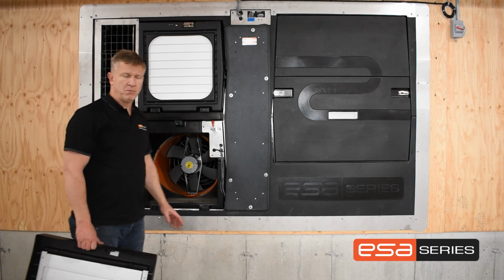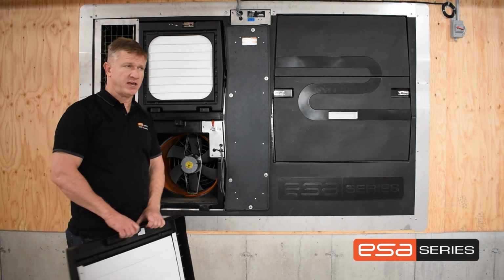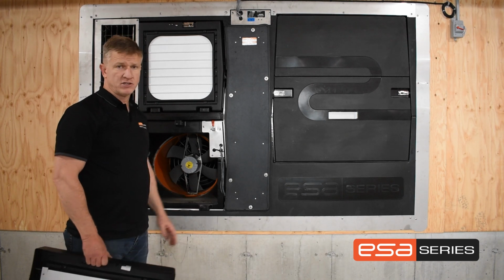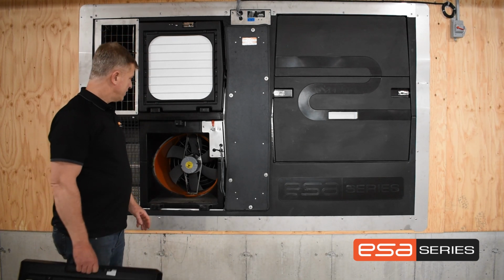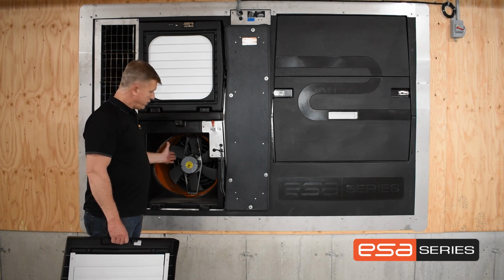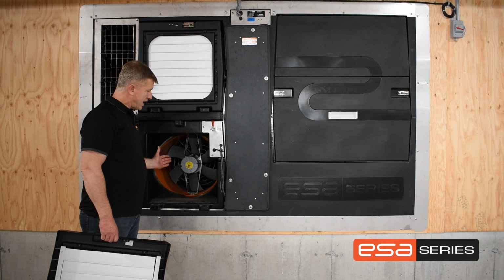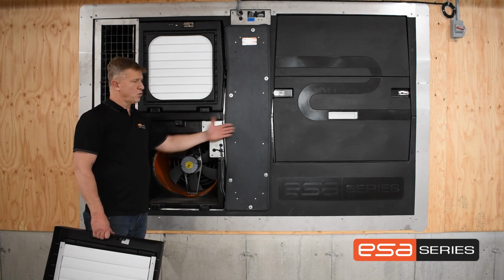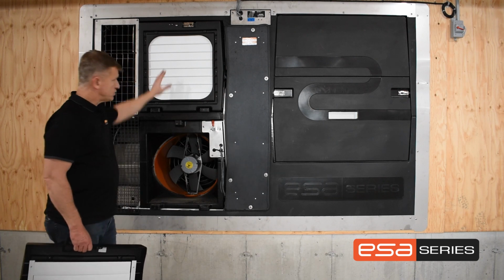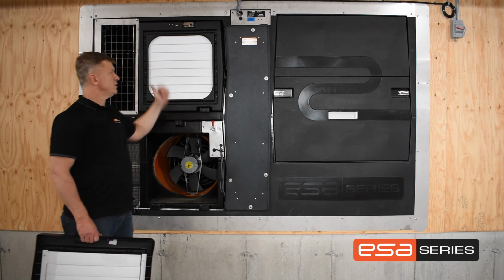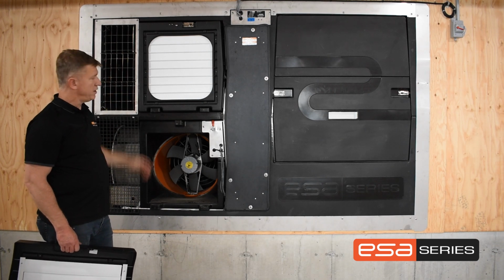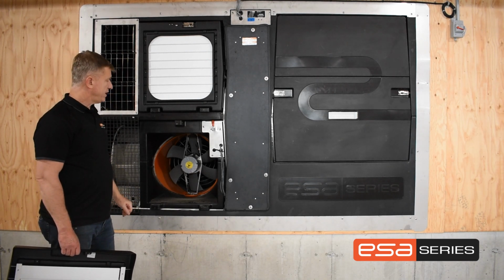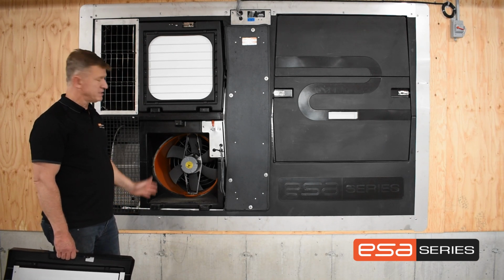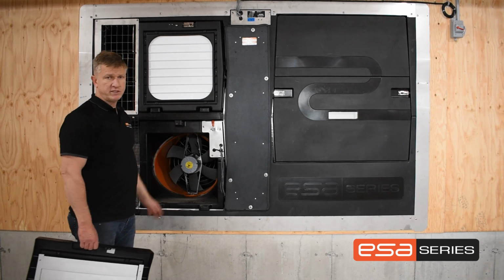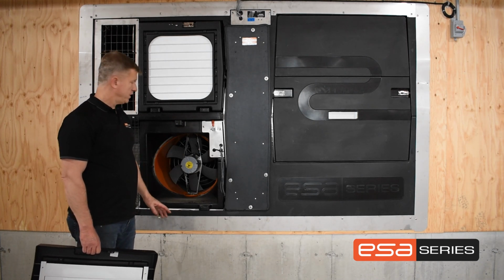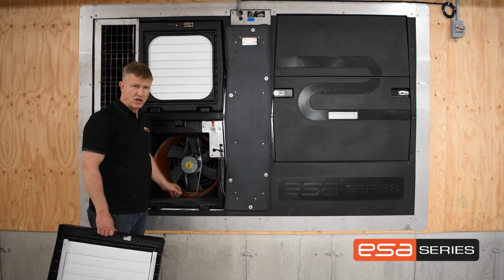These motors are multi-directional, so the heat exchanger has 2 stages of ventilation. We have heat recovery, and then we have exhaust, which we call bypass. In HRV mode, the motor on the bottom, which we call fan 2, is pointing outwards, blowing the air through the cores, up and out. The top fan does the opposite, blowing air into the building, coming in through here, when you're in heat recovery mode. But when the heat exchanger switches to bypass, both motors will turn and point towards the outside and go to pure exhaust mode. Right now you can see this bottom fan is in exhaust mode.